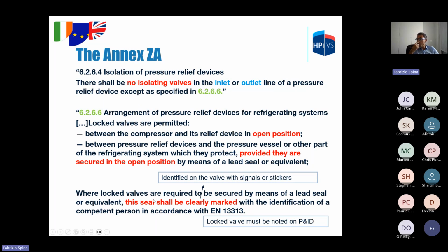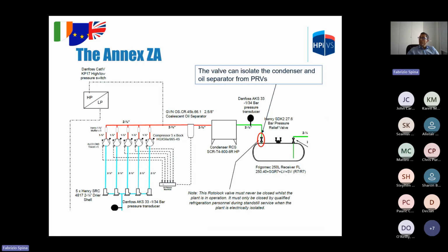When locked valves are installed, this seal shall be clearly marked. That means that it needs to be identified on the valves with signals or stickers, and it could also be useful to note this valve on the P&ID. We have here an example. We have this isolation valve that can isolate the condenser and the oil separator from the pressure source from the compressors. In this case, the valve used is a rotolock valve. The client put a note on the P&ID and put a note physically on the valve with stickers, and so the valve was locked in open position, and this configuration can be accepted.